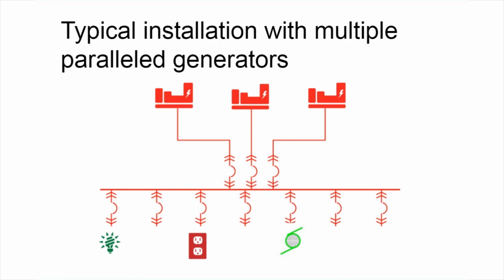Another way of looking at the EPSS is to bring multiple generators in and parallel them together onto a common bus. This can provide a very high degree of reliability and flexibility in your EPS approach. It's a very effective method to utilize an N+1 design where, in this example, two of the generators would serve the base load, and the other one would be completely redundant to the other two, so that if one of those generators goes down, you can still carry 100% of your load. But keep in mind that Article 700 loads should be capable of being picked up by a single generator to meet the 10-second pickup requirement.